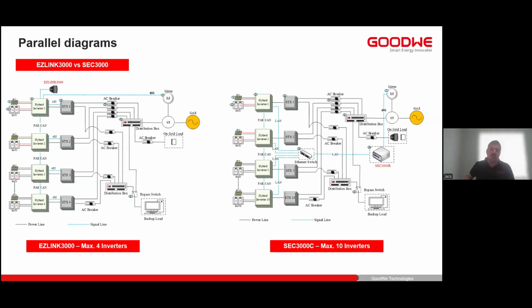The alternative is using the SEC 3000C communication box. With this SEC 3000, we can then parallel a maximum of 10 units. And this is more intended for off-grid applications, as the switching time using the SEC 3000 will be EPS level and not UPS level.